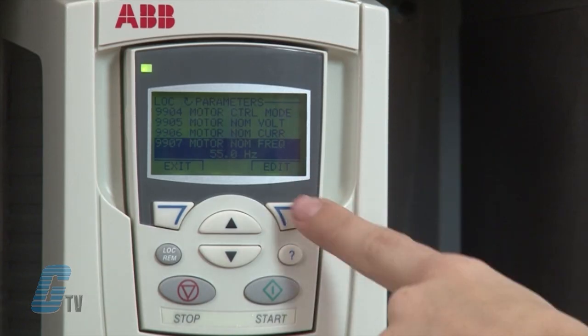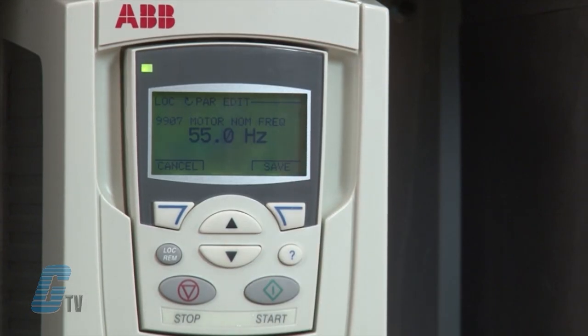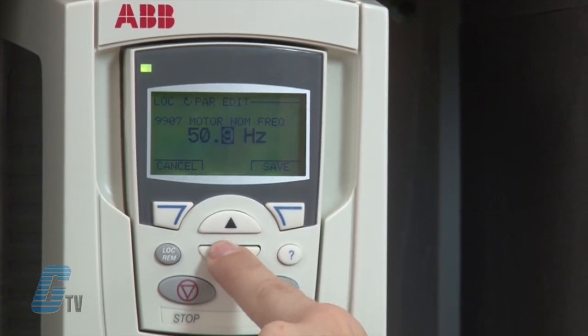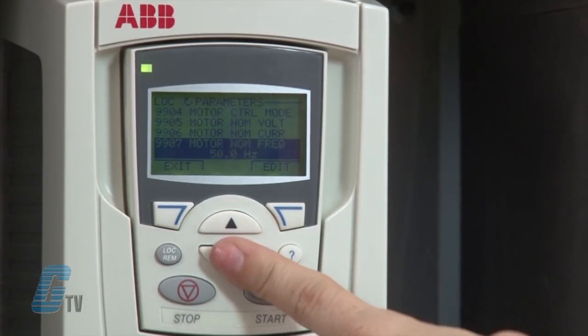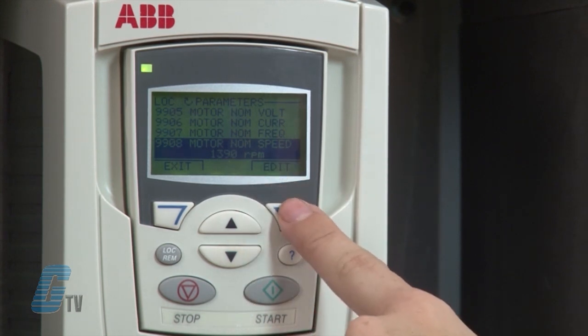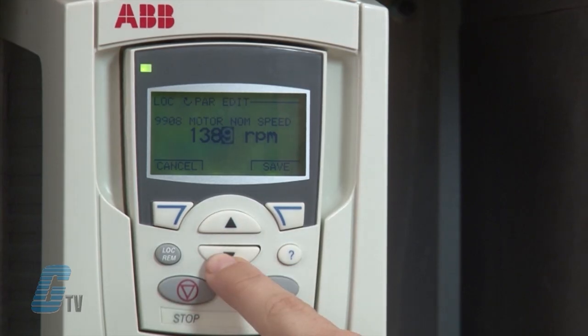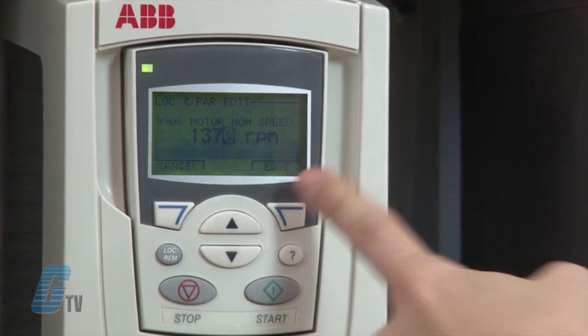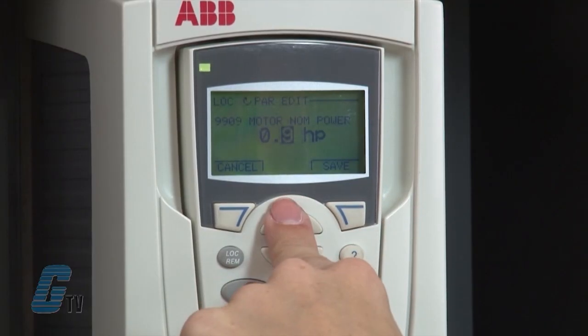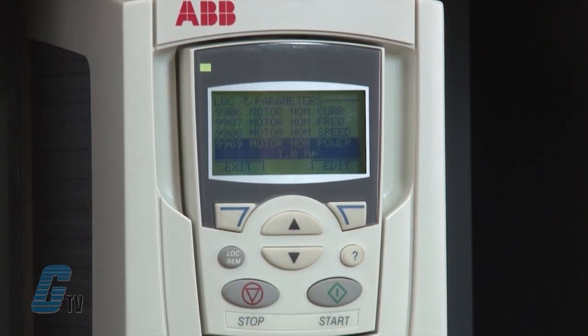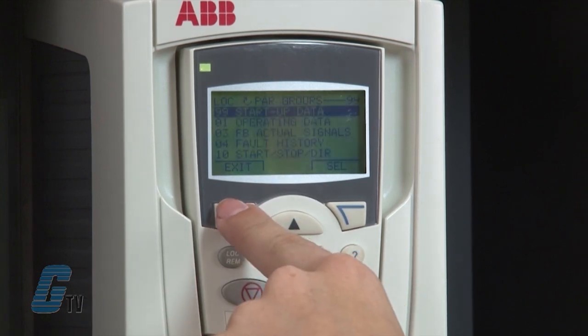Next, I'll go to parameter 99.07 and enter the motor nominal frequency, which is 50 hertz in this case. Then I'll go to parameter 99.08 and enter the motor's nominal speed, which is 1370 RPM in my case. Next, I'll go to parameter 99.09, where I will enter the motor nominal power — this one is 1 horsepower. I have now completed the entry of my motor nameplate data, so I will push the Exit button three times to get back to the main screen.